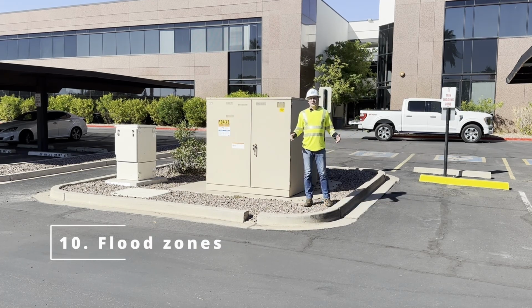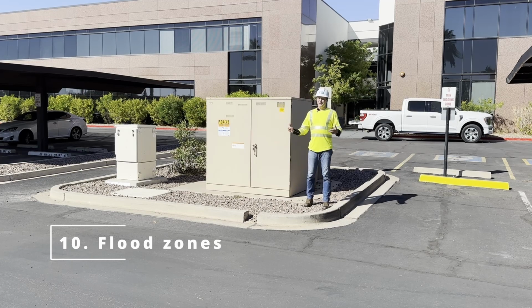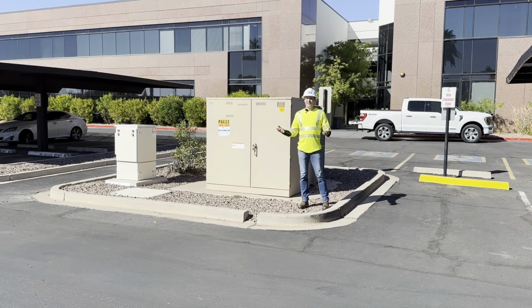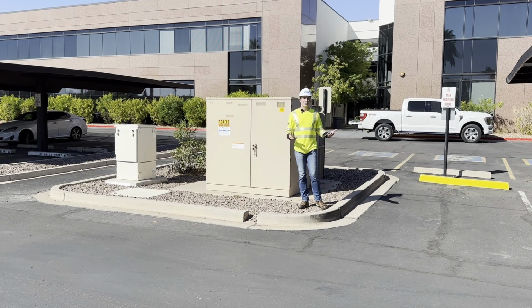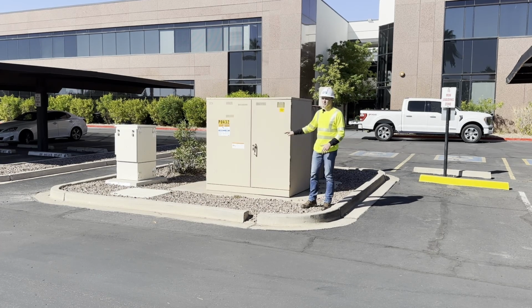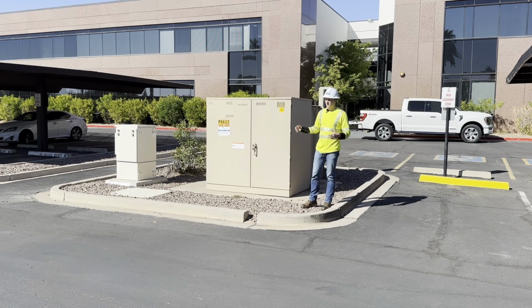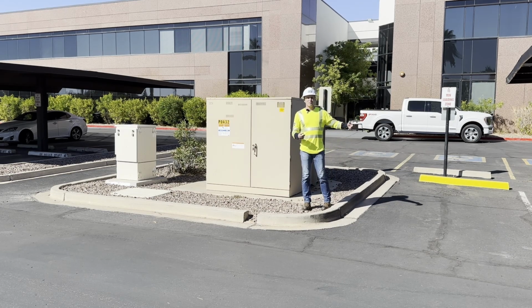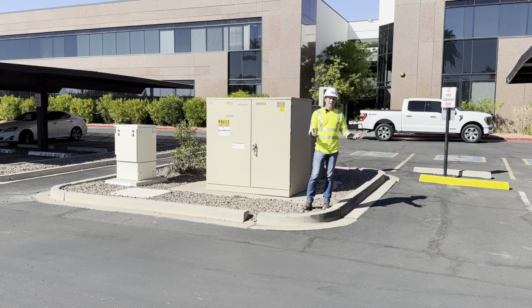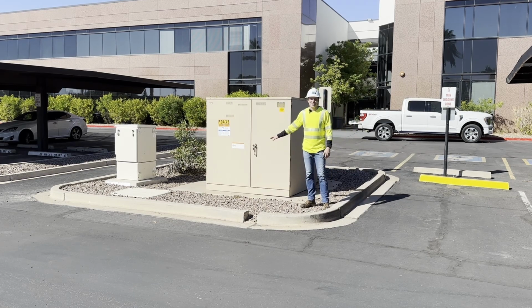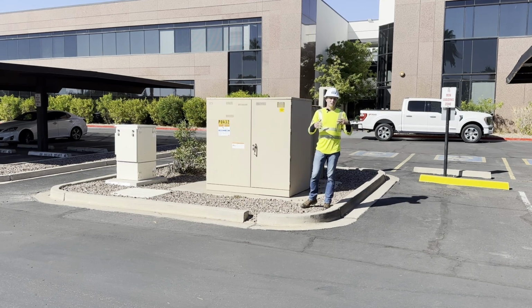Number 10: flood zones. If you live in a part of the country with a lot of rain, hurricanes, or thunderstorms, you probably know this can impact your project—but it also impacts transformer placement. Just like your switchgear and EV chargers as a developer, you never want those in harm's way during a flooding event, and the utility doesn't want theirs in a flood area either in case of a cataclysm or a 100-year flood event.